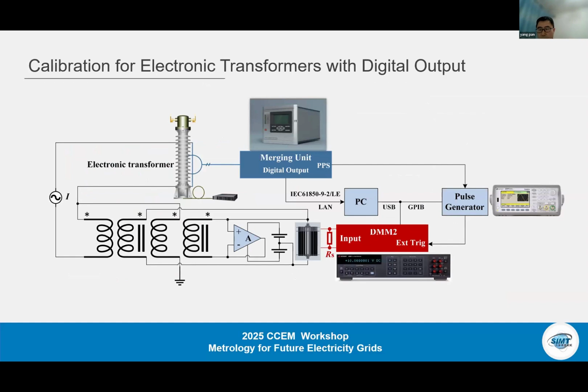So in our approach, one of the DMMs is designated as the independent sampling reference. In order to ensure precise timing, a function generator receives an electrical PPS signal derived from the MU and generates burst pulses to trigger the DMM for sampling. A fiber to Ethernet converter then transfers the data packets from the MU to the computer's Ethernet interface. Finally, a dedicated software platform has been developed to facilitate instrument control, packet capture, signal processing, and result display.